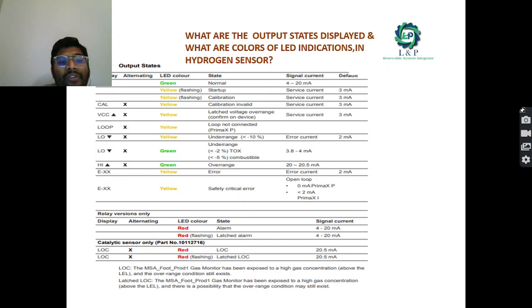For example, if the loop is not connected properly, it will show loop and the yellow LED indication will be there. This you can see in the Prima XP devices. If low with a downward arrow is showing with a yellow LED indication, it is an under range value. If it is showing high with an upward arrow and the green LED indication, it means that it is over range. In the same way, low with the downward arrow and the green LED indication means it is under range. So like this we can easily identify. And if you have any red color indication, it means that there is an alarm. The signal current you can take is up to 4 to 20 milliamps.